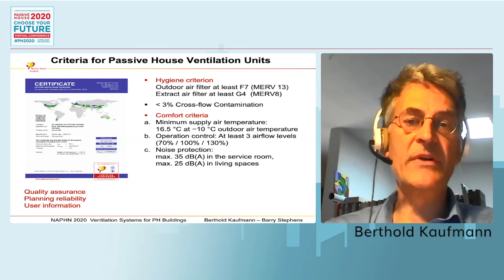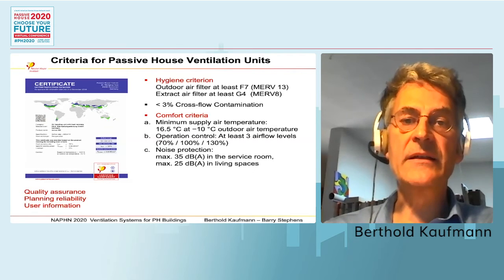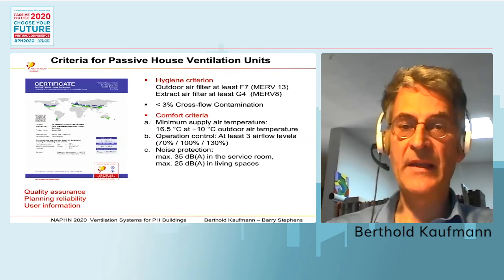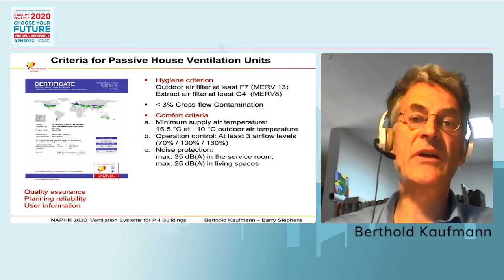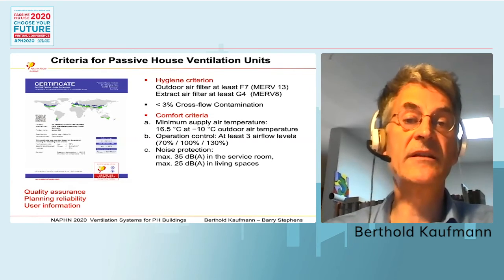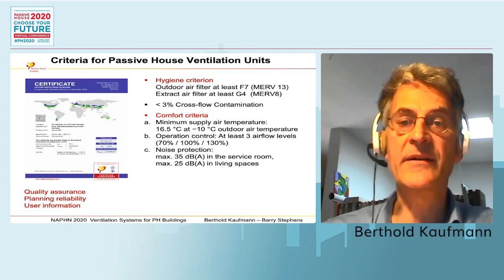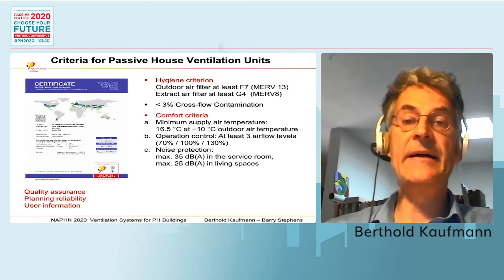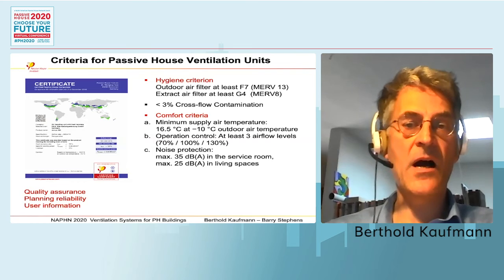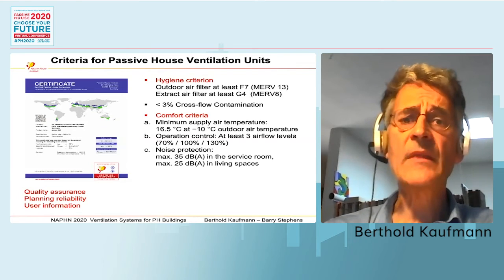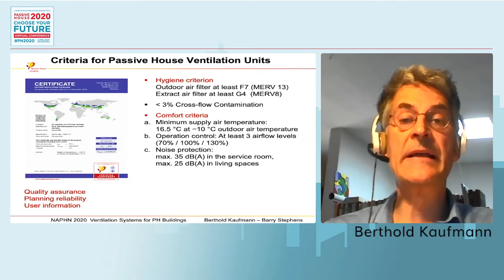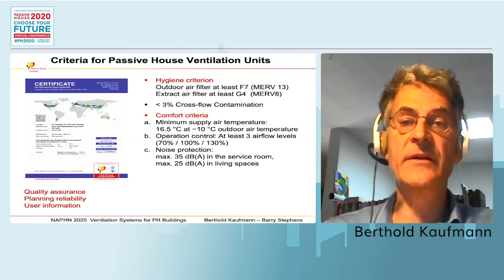Well, the next is comfort. Having a good heat recovery, the supply air temperature is minimum about 17 degrees centigrade, even if you have minus 10 degrees outside. And this is a hard requirement because this is about comfort. If you have lower air temperature for indoor air coming in, people will probably complain about draft air and cold air.